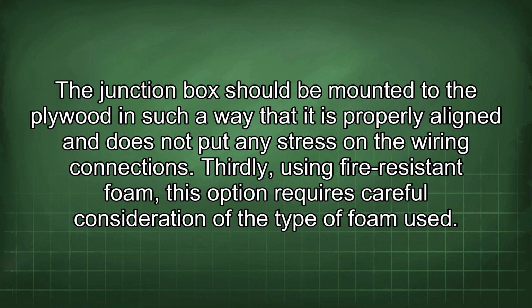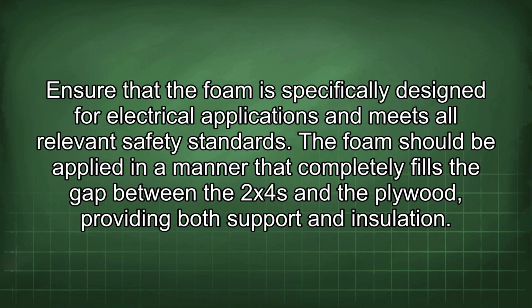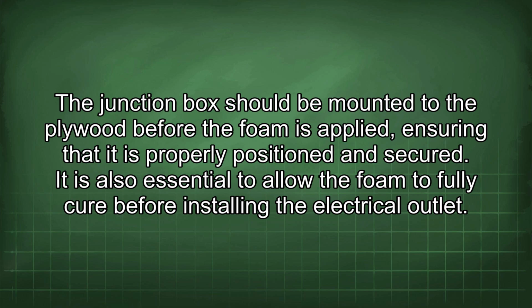Thirdly, using fire-resistant foam. This option requires careful consideration of the type of foam used. Ensure that the foam is specifically designed for electrical applications and meets all relevant safety standards. The foam should be applied in a manner that completely fills the gap between the 2x4s and the plywood, providing both support and insulation. The junction box should be mounted to the plywood before the foam is applied, ensuring that it is properly positioned and secured. It is also essential to allow the foam to fully cure before installing the electrical outlet.